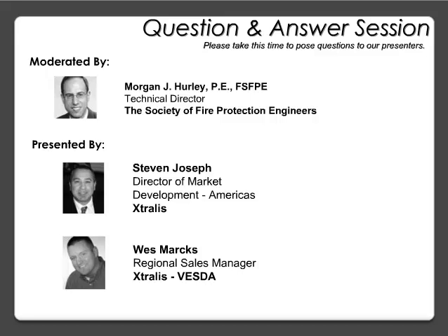One final question. Early in the presentation, when you talked about the different stages of fire development, you also mentioned transport time, and we did have a question asking for a little bit of clarification about what's included in transport time. Sure. So the transport time, that's the time it takes air to get from a sampling hole back to the detector. So it doesn't include alarm time or time until the panel would go into alarm. So just think of it as from when air enters a sampling hole until that air gets back to the air sampling detector, and that's the transport time.